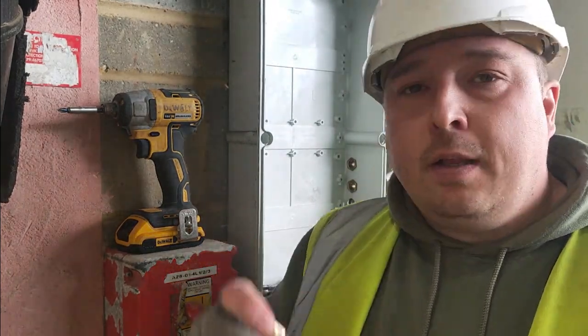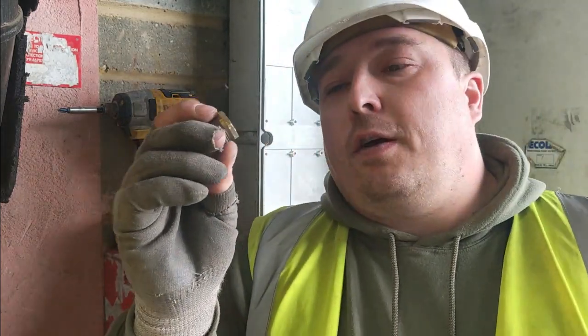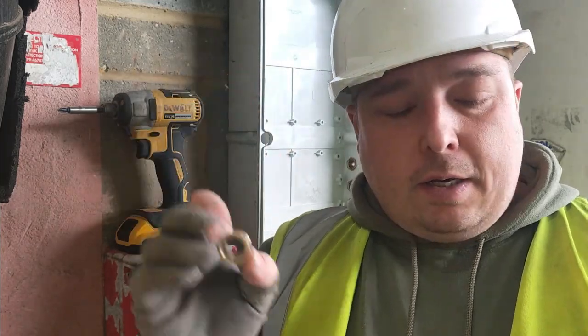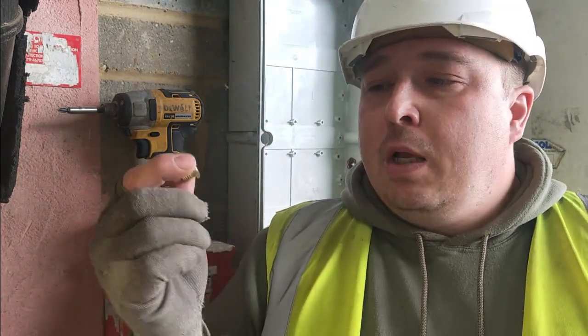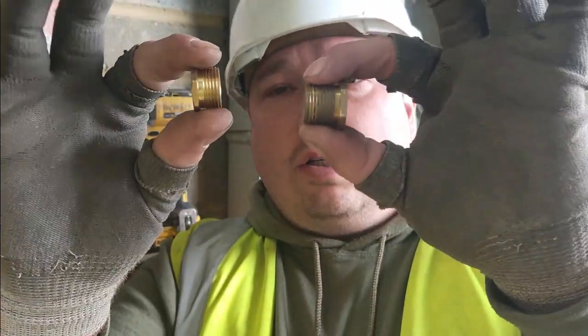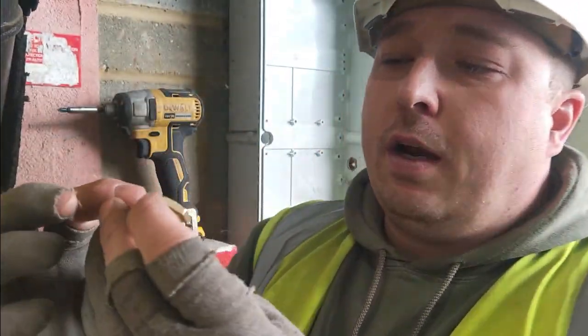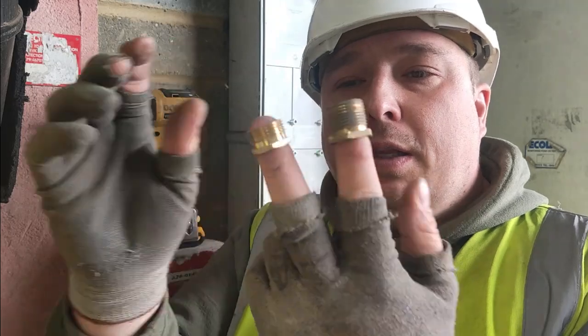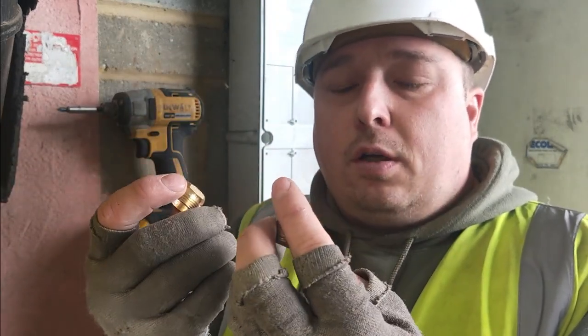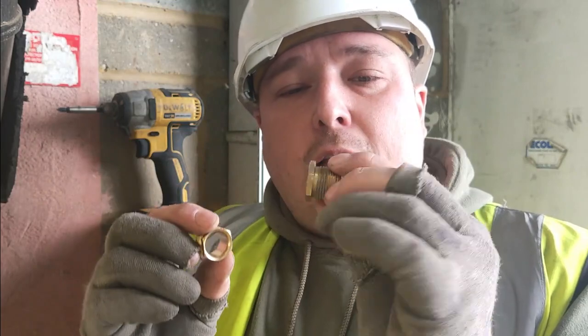This is super interesting. If you have a look here, this is what I've just pulled out. This must be at least 30 years old, and these are the bushes that come out of it. Now, these are the bushes that we use today - not specific to this company or any company, this is just what's being manufactured at the moment. If I give you a side-by-side: this is a long-reach and this is a short one, but you can see the difference in thickness, the difference in quality. They're even a different colour - it's not because it's tarnished. These have a significantly different colour these days, and I'd dare say the composition of the alloy is different now as well. You can actually feel the weight difference, the build quality.